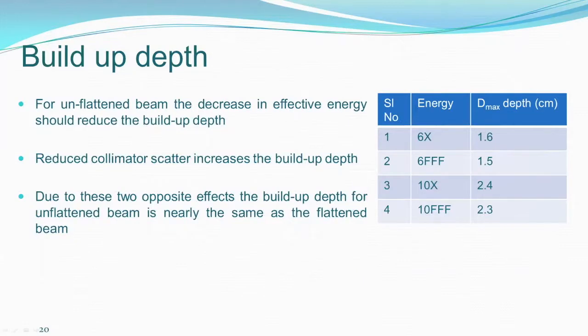The other interesting thing is the buildup depth. When you have an unflattened beam, there is no beam hardening, so you have a lot of soft X-rays. So you tend to think your buildup depth should be much smaller than what you have for a regular 6X, for example. If you have 1.5 or 1.6 for 6X, this is much softer.